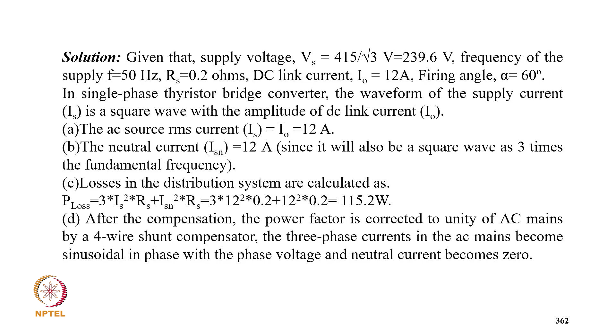So the new supply current RMS fundamental active power component is IS equal to IL1A, that is IS1 cos phi, 12 into 0.9 into cos 30, that is 5.4 ampere. And in this case, after the compensation, 3-phase currents in the mains are balanced, sinusoidal, and neutral current becomes 0. The losses in the distribution system are now 3 IS squared RS plus ISN squared RS, 5.4 squared into 0.2 into 3, plus 0, so it becomes 17.496 watt.